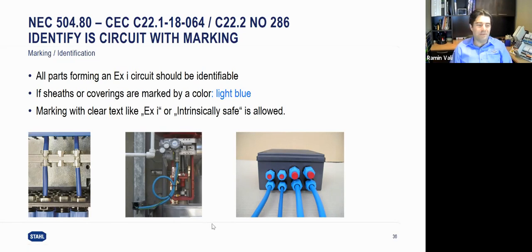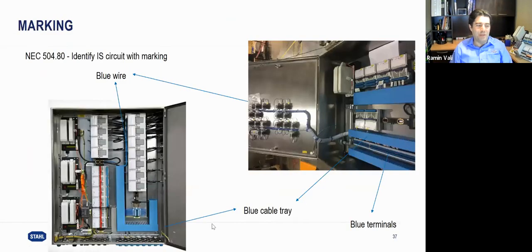That's why we see a lot of times companies use light blue glands, light blue ducts, light blue wirings. These are the panels, for example, built by Stahl. You can see from the terminals of the I/O card, the ducts, and the cables, the wiring is all in blue colors, and the glands on the bottom. So for maintenance, it's much easier to look at it as an intrinsically safe signal and do live maintenance, which is one of the main advantages of having this intrinsically safe.